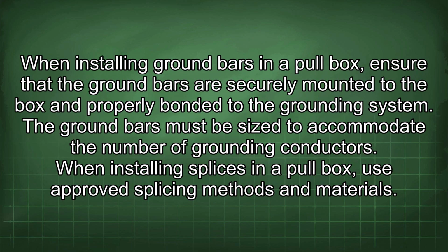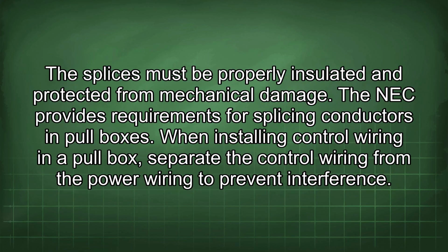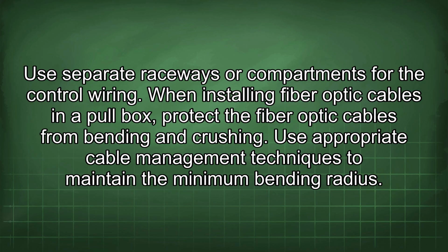When installing ground bars in a pull box, ensure that the ground bars are securely mounted to the box and properly bonded to the grounding system. The ground bars must be sized to accommodate the number of grounding conductors. When installing splices in a pull box, use approved splicing methods and materials. The splices must be properly insulated and protected from mechanical damage. The NEC provides requirements for splicing conductors in pull boxes. When installing control wiring in a pull box, separate the control wiring from the power wiring to prevent interference. Use separate raceways or compartments for the control wiring.